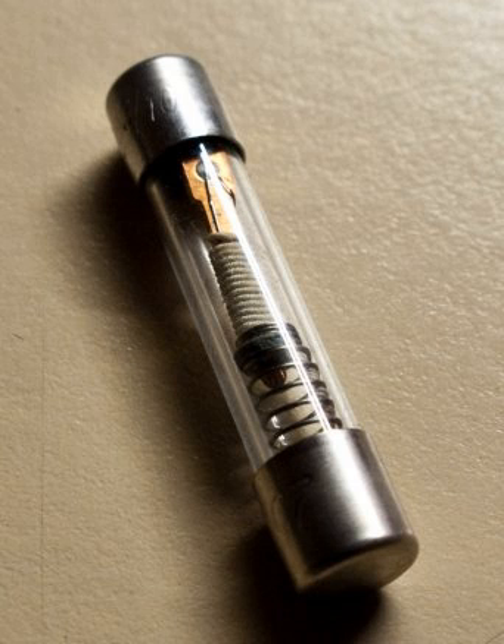If too high a current flows, the element rises to a higher temperature and either directly melts, or else melts a soldered joint within the fuse, opening the circuit. The fuse element is made of zinc, copper, silver, aluminum, or alloys to provide stable and predictable characteristics. The fuse ideally would carry its rated current indefinitely, and melt quickly on a small excess. The element must not be damaged by minor harmless surges of current, and must not oxidize or change its behavior after possibly years of service.